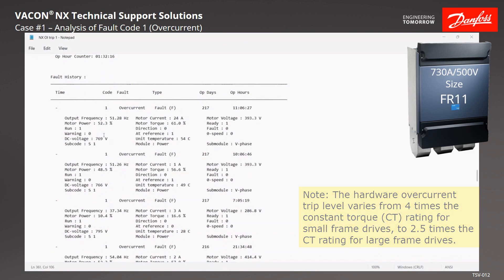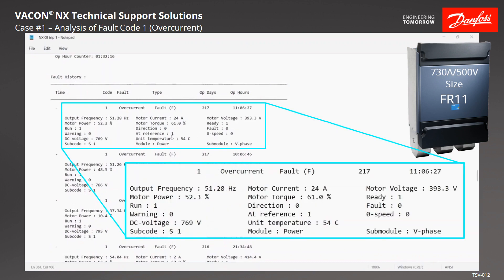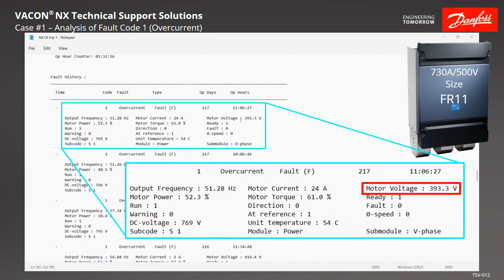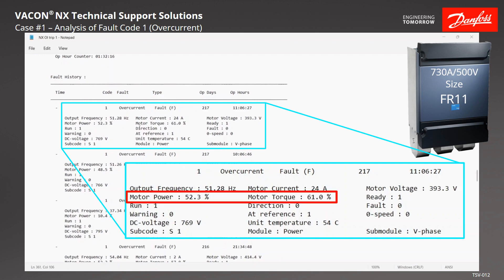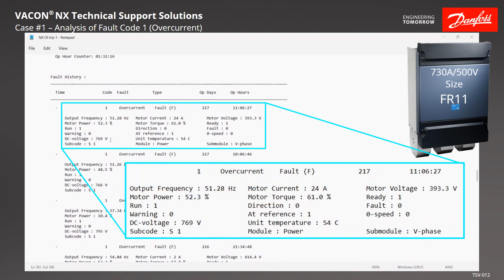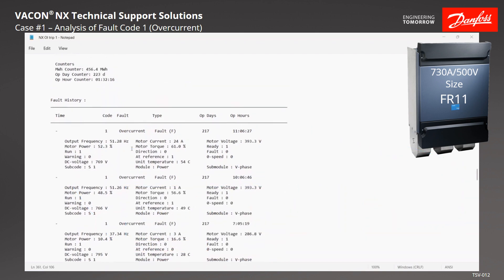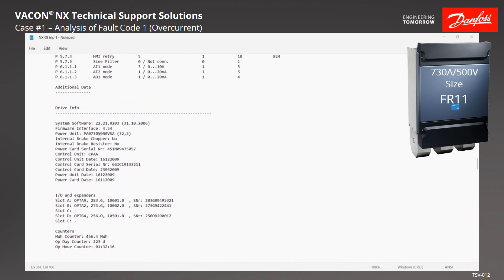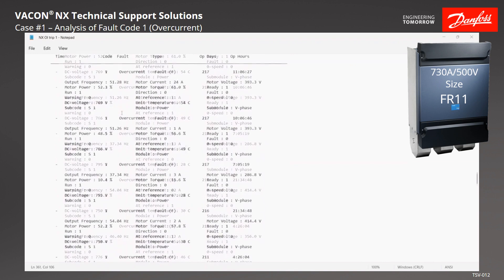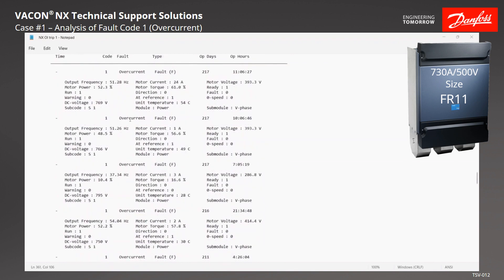Looking at other data that might be a little weird: the 51.28 Hz looks about right, and voltage is about right for that frequency. Power and torque we can't confirm either way, so we'll leave those. The next thing that looks odd is DC bus voltage at 769 volts. We know this is a 500-volt unit — a typical DC bus would be close to around 680 volts.